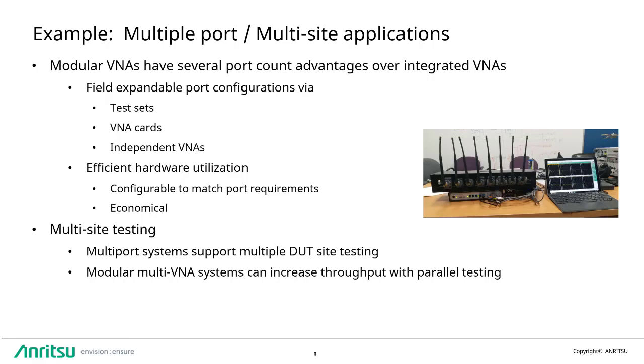Whether the expansion is supported through chassis extensions, additional VNA cards in a backplane, or additional independent VNAs, modular architectures are able to test multi-port DUTs in a more efficient and economical way than integrated VNAs.